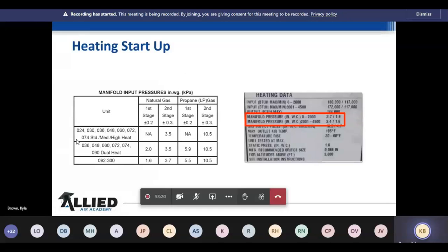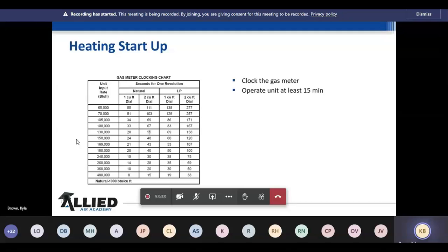And here are our manifold gas pressures, and these are all in the service manual, and that's where you'll check it. And if you put an LP kit in there, it's going to give you the pressures for that, and then it'll give you a sticker to put on the outside as well. And then you really want to clock your meter, but let it run 15 minutes, and let's make sure we're getting all the capacity out of it that we can, especially in the northern areas and up in Canada where it gets extremely cold and you actually have a heater inside the vestibule panel area. You really want to make sure you're putting out everything that unit can. It is imperative that we do that.